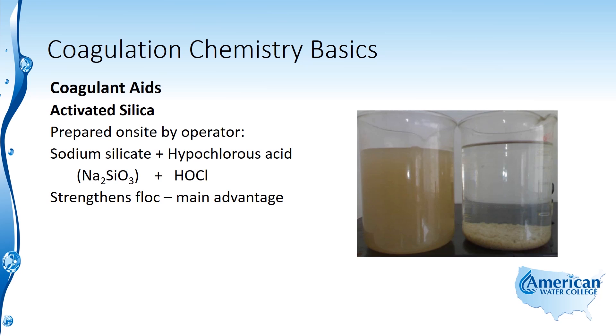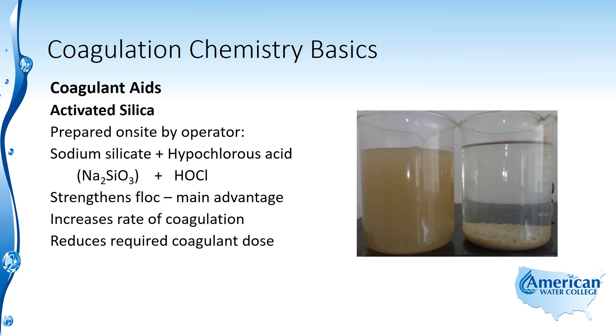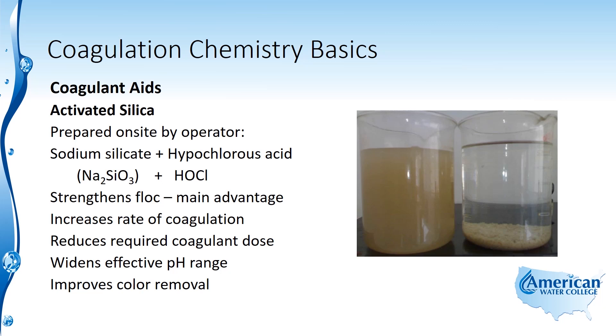Any floc that carries over the sedimentation basin and gets filtered will also stay together and be easily filtered out. Activated silica also increases the rate of coagulation and reduces the required coagulant dose, as well as widening the effective pH range of the coagulant. For example, aluminum sulfate has a limited pH range in which it works, so activated silica can increase that range.